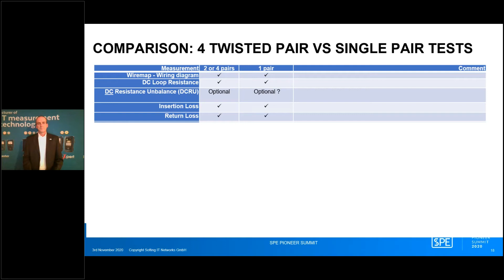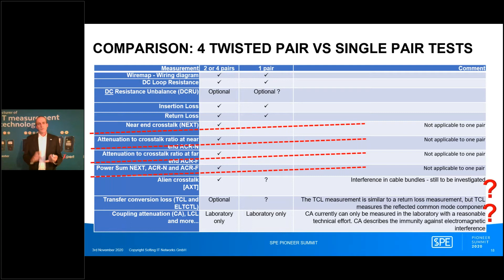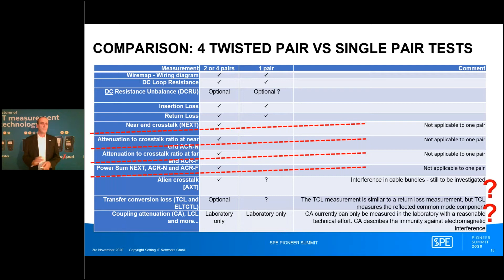Then there's alien crosstalk. Alien crosstalk is the crosstalk between cables and cable bundles. We come to that in a later slide. And there are things that try to measure the electromagnetic immunity of cables. Transfer conversion loss, TCL, and ELTCTL, basically work well on unshielded cable, but there are still questions and limit discussions on shielded cables. Coupling attenuation and LCL and so on are more laboratory measurements that cannot really be measured in the field. I'll show you pictures of this measurement later on. So you see there are still some question marks here, which we need to answer mainly in the new edition of this standard.